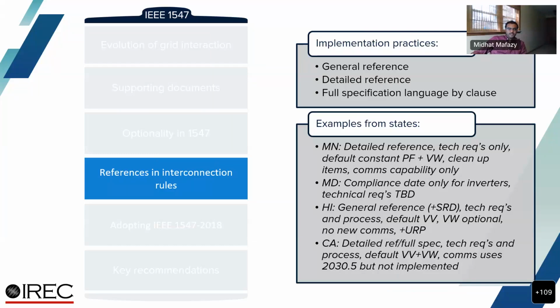I will also say that for all these states, at least for inverter-based systems, they are following category 3 for ride-through and category B for reactive capability. California is the only state that has specified comms to use the 2030.5 protocol. All other states only require comms capability without defining specific protocols.